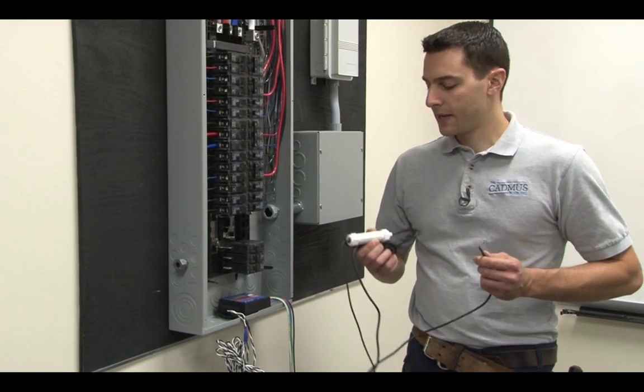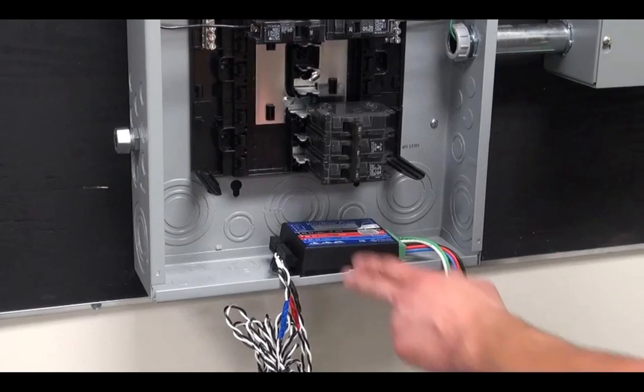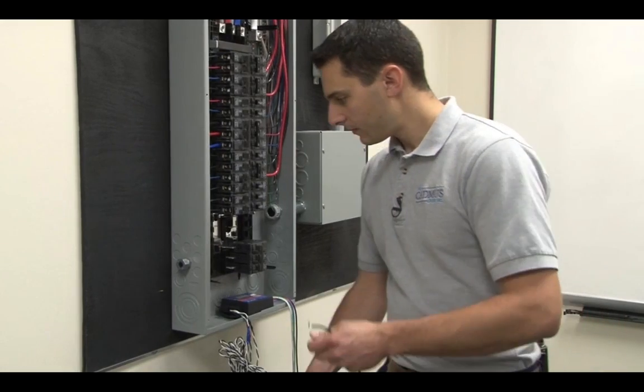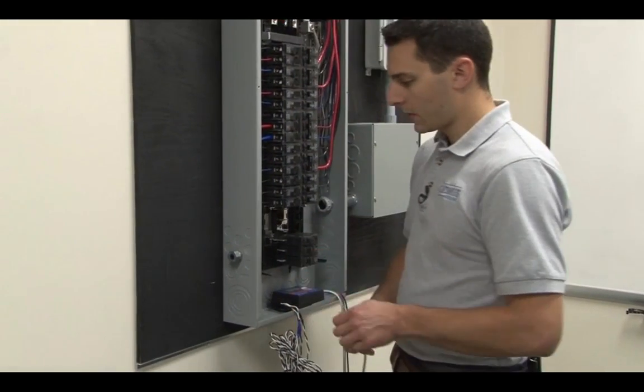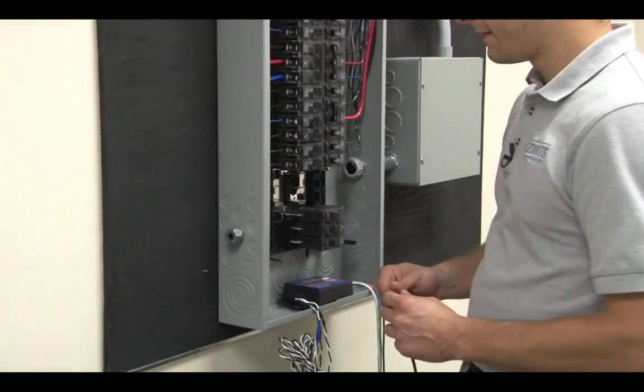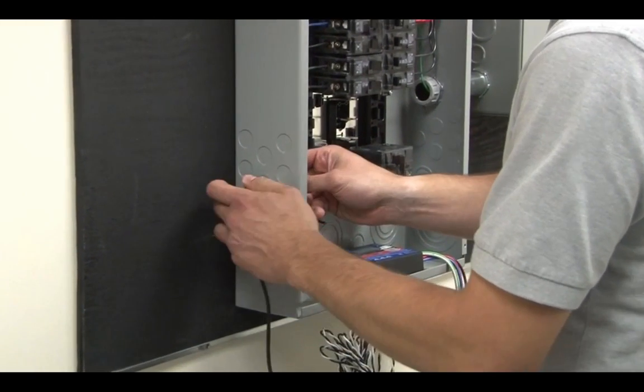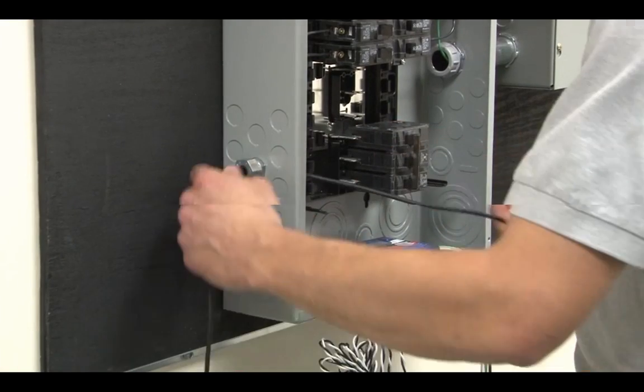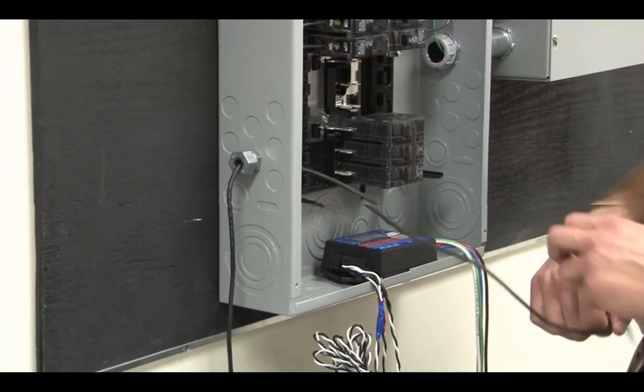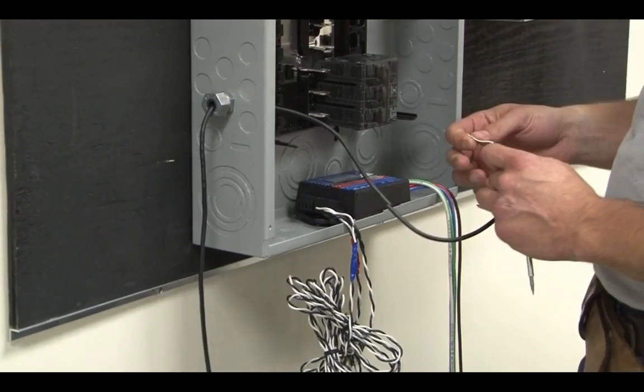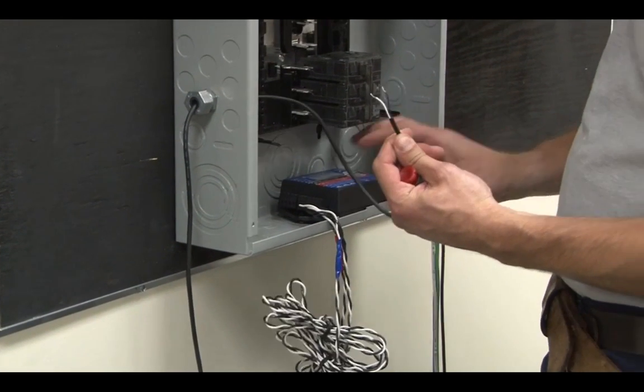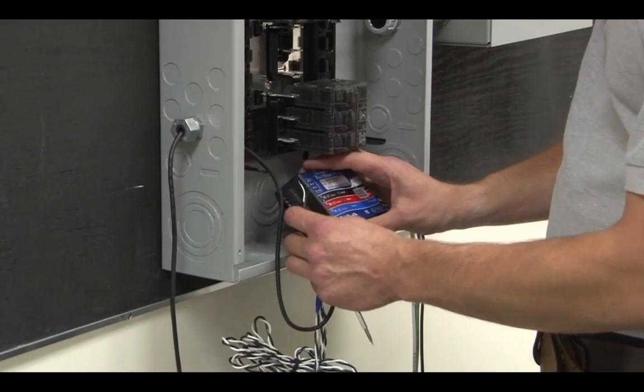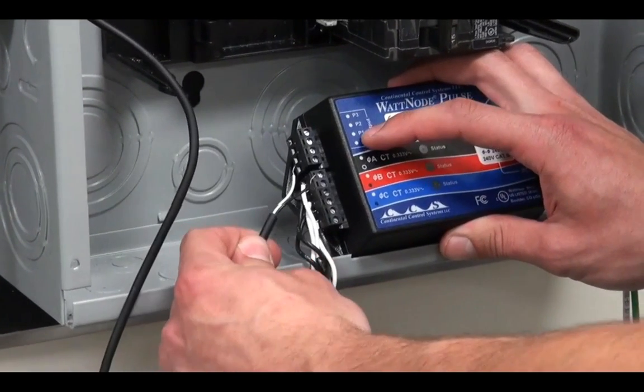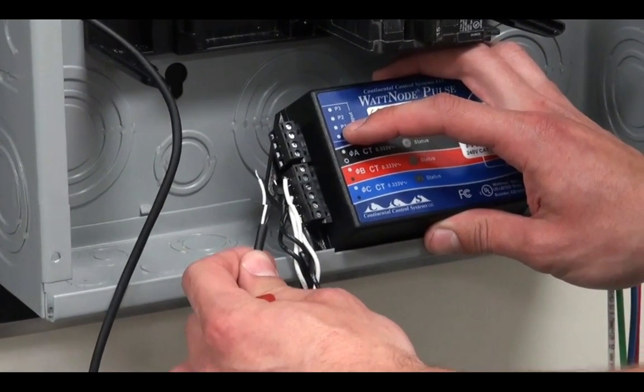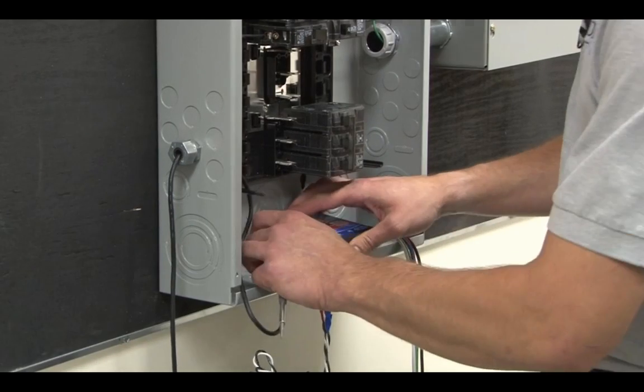We can now run the Onset pulse input adapter cable to our Wattnode. We'll do so using the listed fitting to bring our cable into the panel board, and we'll wire it directly to the Wattnode. This cable has a black and white conductor. The black will be connected to the common, and the white wire will be connected to P1. Normally we will not use P2 and P3.